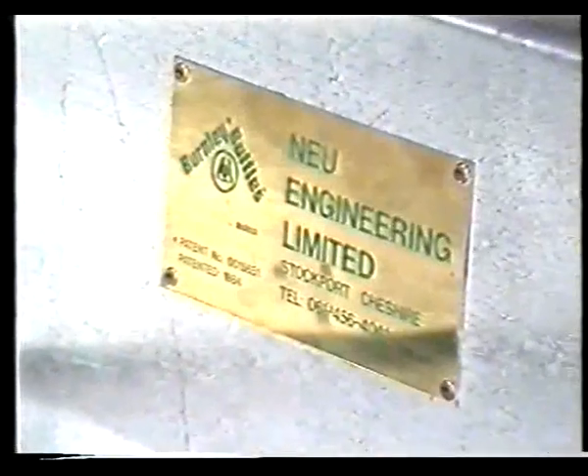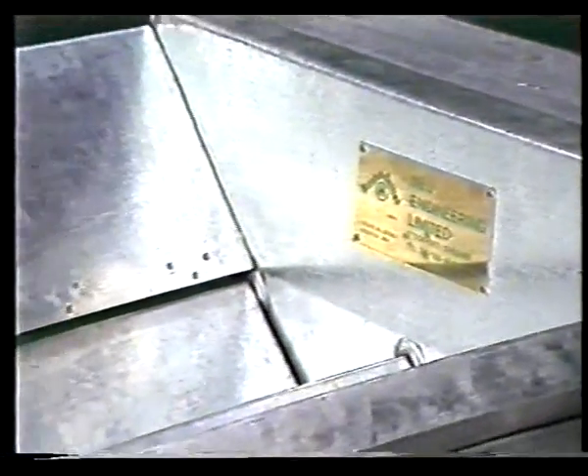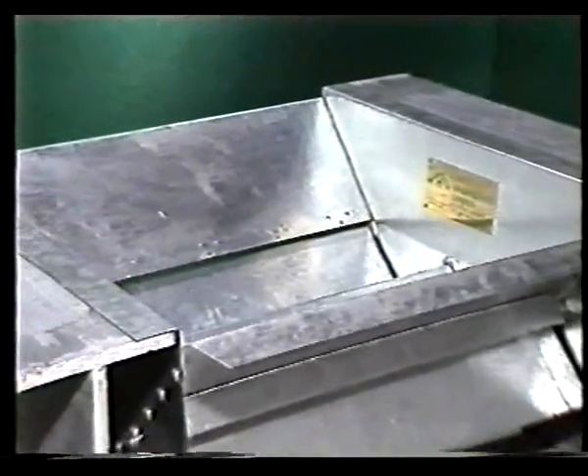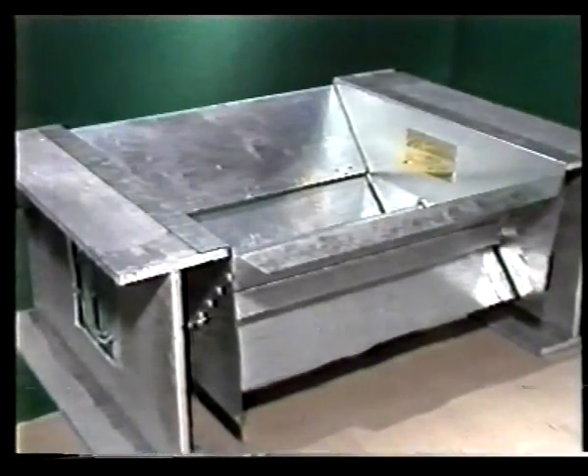The NEU Engineering solution has been achieved by fitting 12 Burnley Baffle modules below the existing grating. Burnley Baffles comprise a series of pivotally mounted blades and fixed deflectors. Simple to install, automatic in operation, and free from maintenance, the modules fit beneath a hopper grating to suppress and contain dust without impeding material flow.